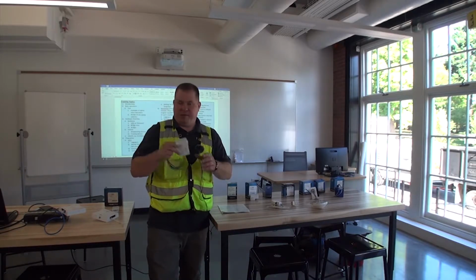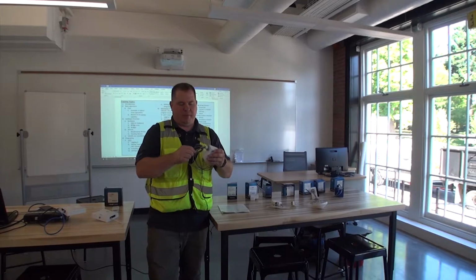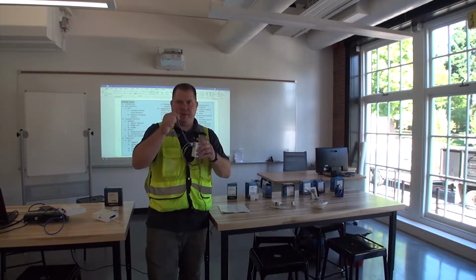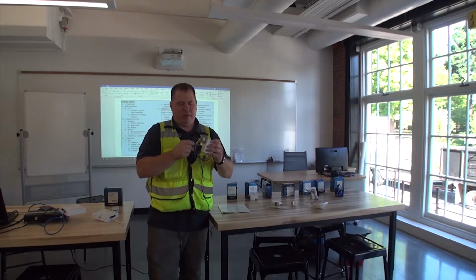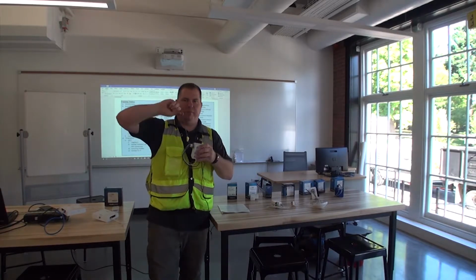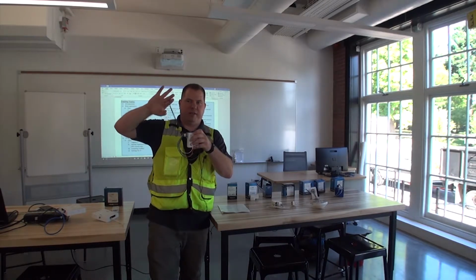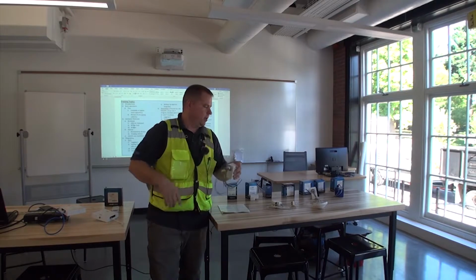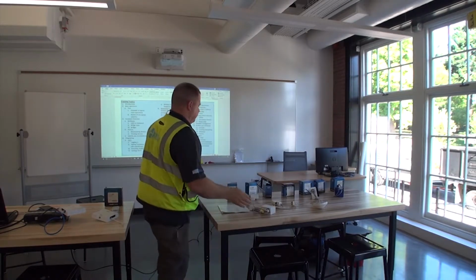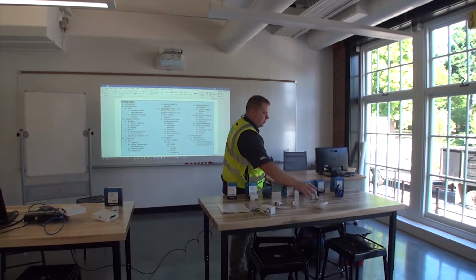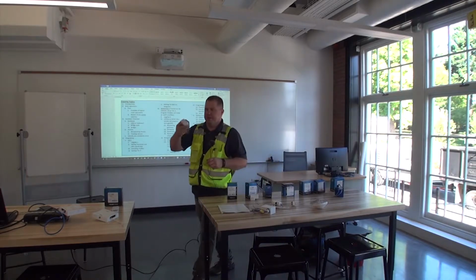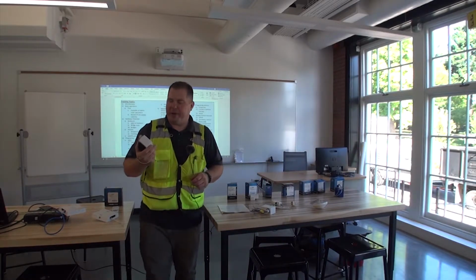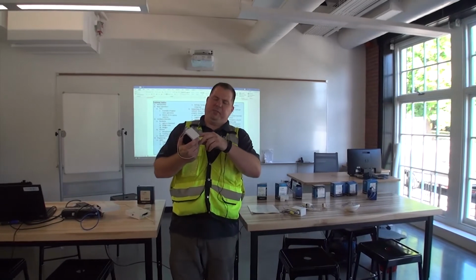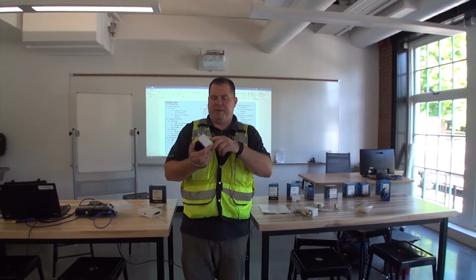The NPP16D is dimming, right? So it still has the NPP16 relay, it's got the switch leg in it, but it also has blue and gray 0 to 10 volt dimming. It's still a standard power pack, and it does produce power. This one with the fins on it is a specialty power pack. It's an NSP5 PCD ELV 120.